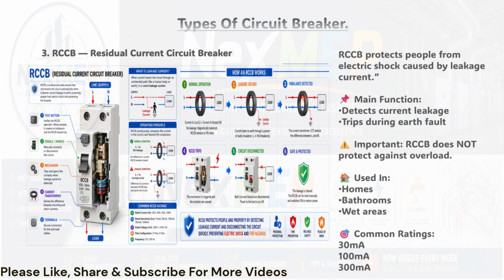Now we come to the RCCB, Residual Current Circuit Breaker, and this one is all about human safety. Here's the core concept. In a healthy circuit, the current flowing through the live wire and the current returning through the neutral wire should be equal. If they're not, if there's a difference, it means current is leaking somewhere. That somewhere could be Earth, or worse, a human body.